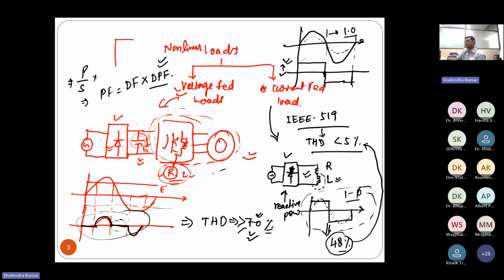Fundamental power factor, I would say. So the fundamental current after filtration is in phase with the voltage. But the rest of the current appears as a high frequency current, because now the current is changed. If you talk about the total RMS current, it is now I1 plus IH. What is IH? Harmonic current, high frequency current. I1 is your fundamental current. But what about the IH? IH is the harmonic current.